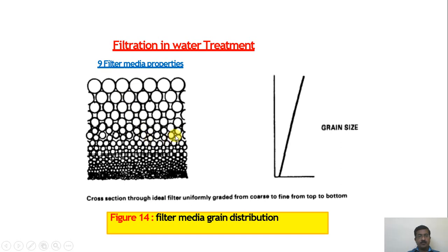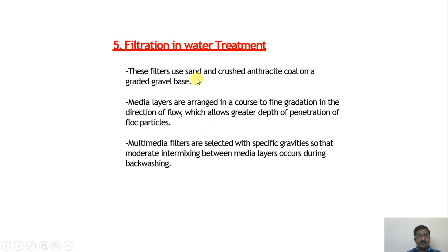Filter media should be well-graded, with uniformly graded coarse-to-fine sand from top to bottom across different layers. The grain distribution of filter media forming various layers helps achieve effective filtration. Media layers use sand, crushed anthracite coal, and gravel, arranged in a coarse-to-fine gradation in the direction of flow, allowing greater depth of penetration of floc particles. Multi-media filters are selected with specific gravity so that moderate intermixing between media layers occurs during backwashing.